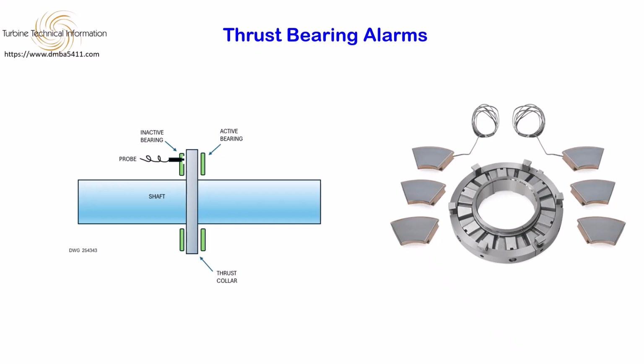Consequences of improper setup. When a thrust channel is not set up during commissioning or is configured incorrectly, it often leads to nuisance alarms, or the equipment is not protected. If the set points do not account for the specific zero voltage of the active thrust position, the system cannot provide the appropriate settings needed to give the bearing the protection it needs, potentially failing to stop the machine before catastrophic wear occurs.